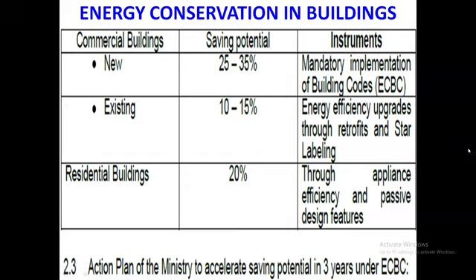It is applied to the HVAC side also, because HVAC, heating, ventilation and air conditioning, consumes almost 50% of the energy in commercial buildings, and residential buildings are also falling in line. People who were using ceiling fans have started switching over to air conditioners, and air conditioners which were consuming almost 2 kilowatts per ton have come down to 1 kilowatt per ton, thanks to the inverter mode of operation. A lot of inputs are coming to the domestic segment from the industry side.